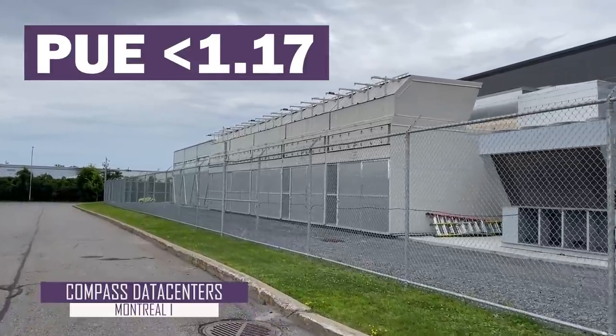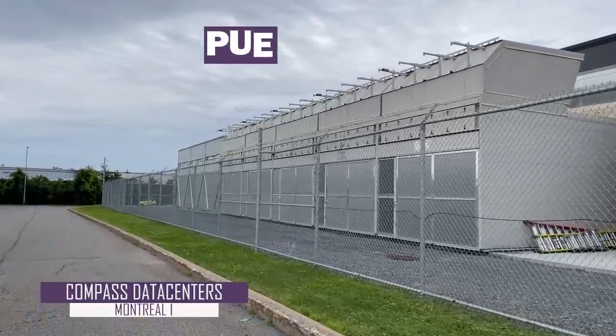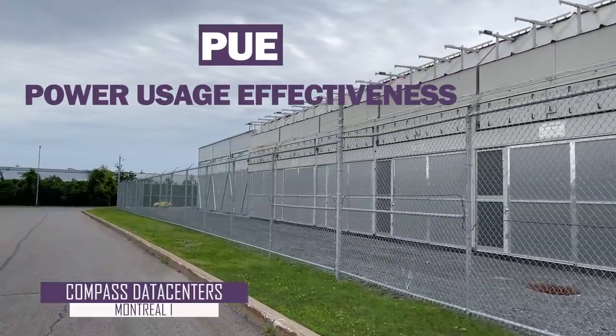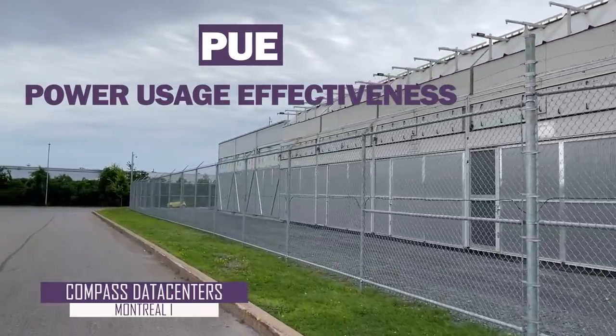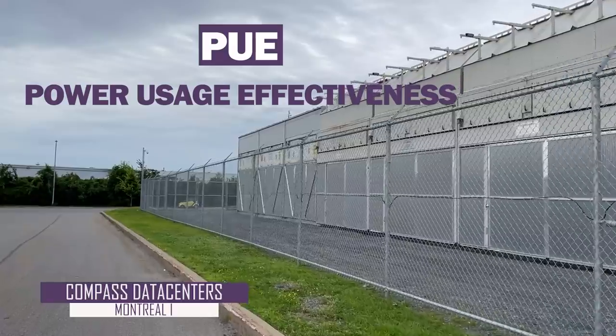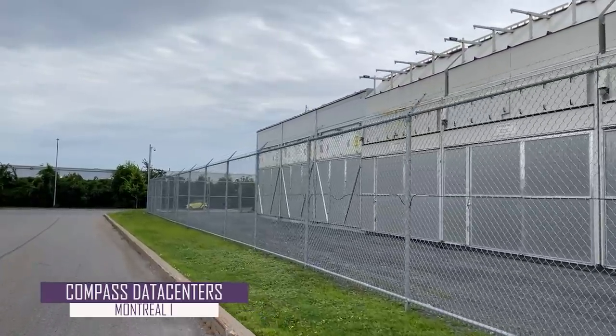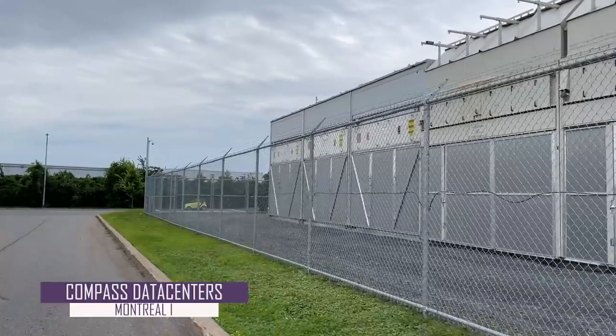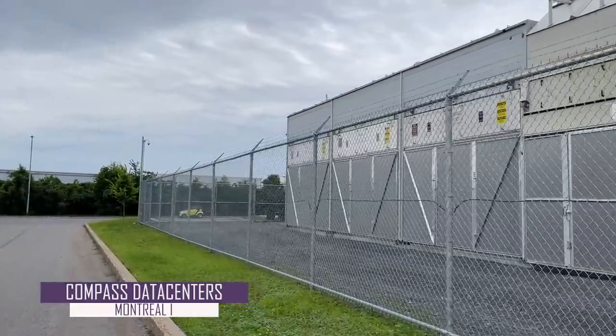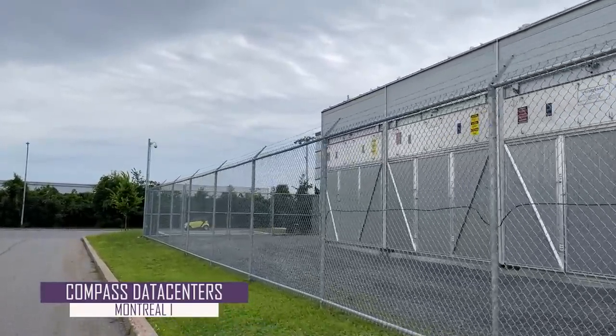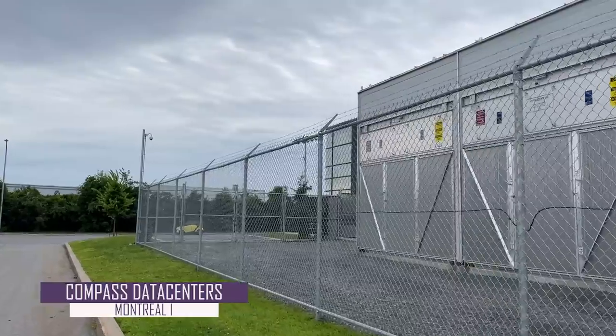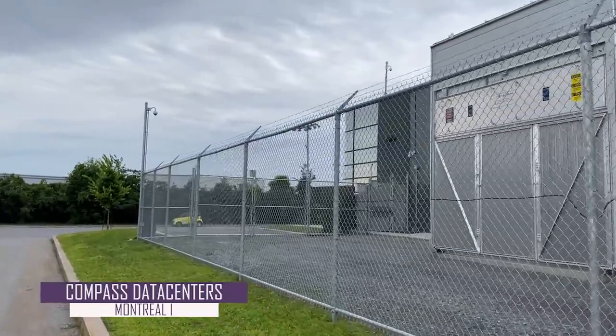industry average. PUE, which stands for Power Usage Effectiveness, is an efficiency metric that is the ratio of the total amount of electricity consumed by a data center to the amount of electricity delivered to its equipment. PUE is always equal to 1 or greater, but the closer PUE is to 1, the more efficient the data center.